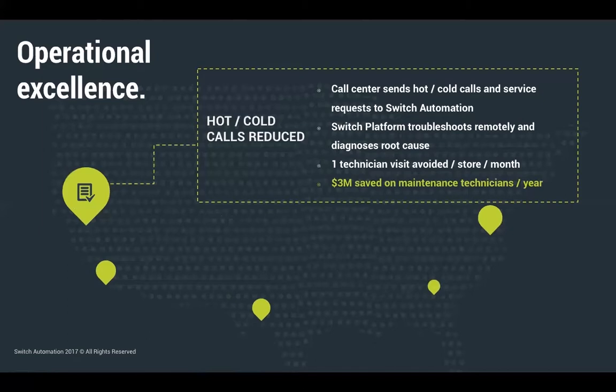It's a huge number. If there is in fact a mechanical issue in those stores, platform users can leverage multi-conditional logic rules called fault detection and diagnostics to find the root cause of the problem—in other words, which piece of equipment is actually causing the occupant's discomfort call.